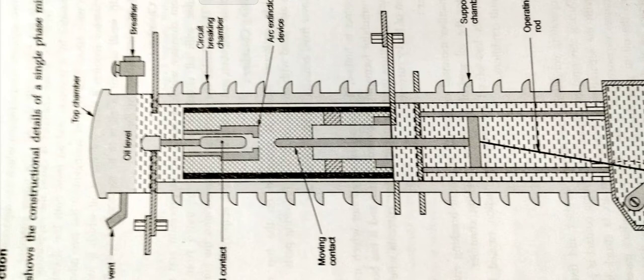The moving contact is hollow. It consists of cylinder which moves down over a fixed post piston. The turbulator forms an arc control device and it has both axial and radial vents. The axial venting ensures the interruption of low current whereas radial venting ensures interruption of heavy currents in current breaking chamber.